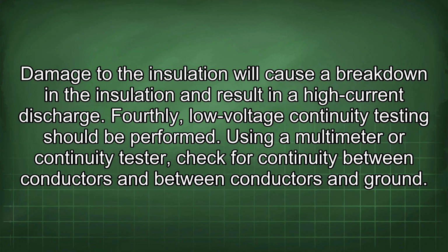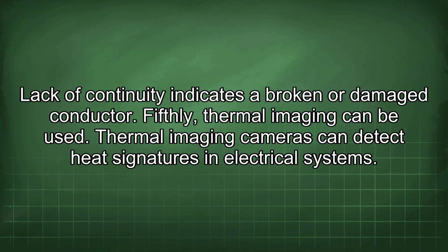Fourthly, low voltage continuity testing should be performed. Using a multimeter or continuity tester, check for continuity between conductors and between conductors and ground. Lack of continuity indicates a broken or damaged conductor.